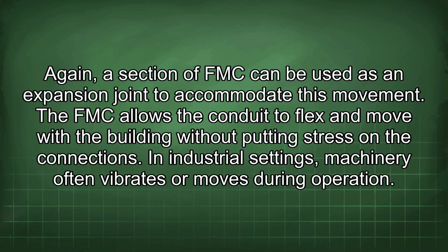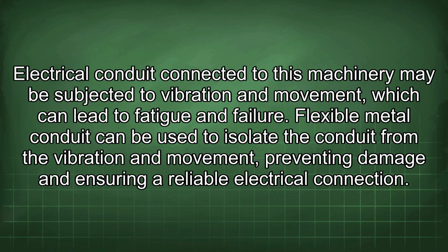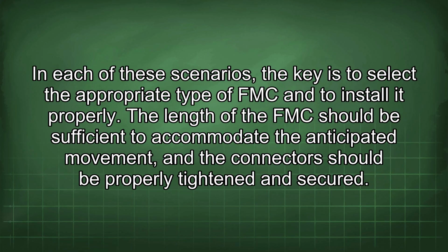In industrial settings, machinery often vibrates or moves during operation. The electrical conduit connected to this machinery may be subjected to vibration and movement, which can lead to fatigue and failure. Flexible metal conduit can be used to isolate the conduit from the vibration and movement, preventing damage and ensuring a reliable electrical connection. In each of these scenarios, the key is to select the appropriate type of FMC and to install it properly. The length of the FMC should be sufficient to accommodate the anticipated movement, and the connectors should be properly tightened and secured.